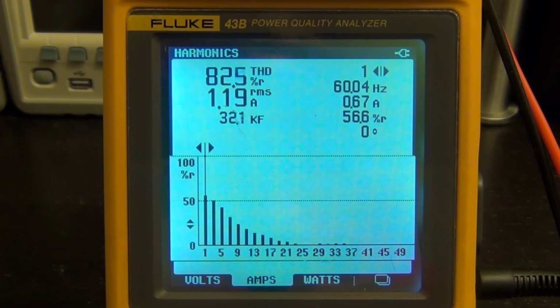As I mentioned, it's not going to have power in the second harmonic, and I can move it over. Check it out, second harmonic, nothing. There's no power going through the second harmonic. Go to the third harmonic, and now you can see again lots of current going through its third harmonic being at 180 Hertz. A lot of power there. That's why your total power factor is so poor.